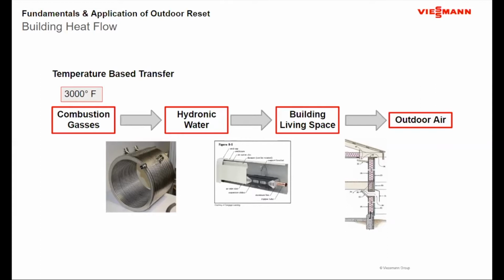When we look at this heat flow from the combustion chamber to the outside, this point here is fairly well tied into a fairly tight band on temperature. Same thing as with combustion. In most cases, the building living space is usually a tied-in point as well. Here I have 70 degrees Fahrenheit. If you're running off the metric system, you may be looking at maybe 20 or 21 degrees Celsius, which is pretty close. So there's not going to be a lot of variation here either. But when we look at the entire process, from the aspect of what we do, there really is one point that we can control: the hydronic water temperature. We can design and we can control what that temperature is doing, but it becomes a question of what we are going to do with that water temperature.